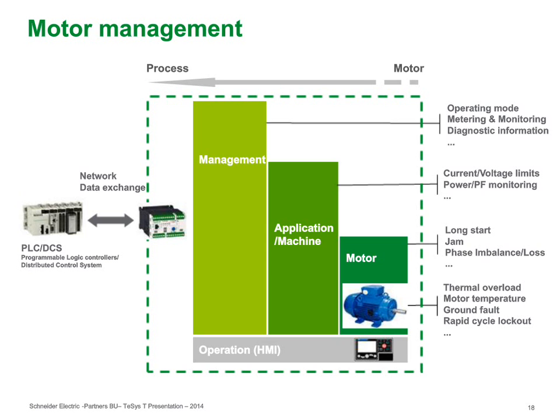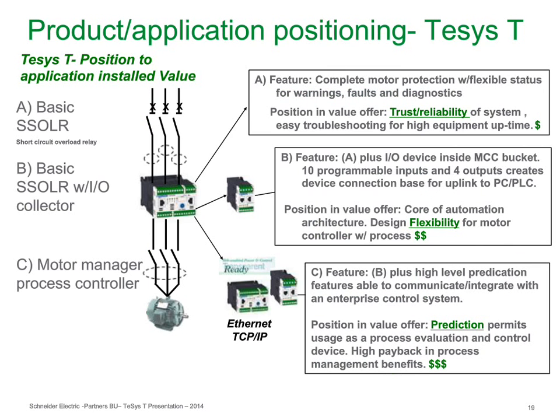So again, we take a look here at other usages, and again, this is more from a design standpoint. We've talked about using it as a basic short circuit overload relay, but one of the beauties in point B here is the fact with 10 inputs and 4 outputs, I can actually have fully networked communication to other devices that might be adjacent to where the motor's running. So solenoids, valves, pressure settings, other switches or relays that you might have that control a process, you can actually use the connections into TeSys T to put these into the network. So having this kind of I/O flexibility, very, very useful in process.